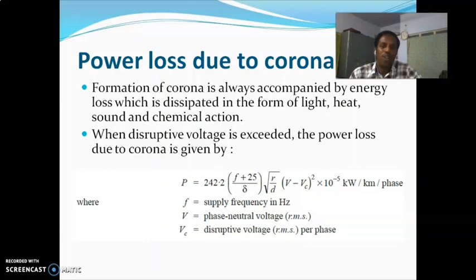So this power loss will be calculated from the given formula. P is equal to 242.2 by delta into (f plus 25) into square root of r by D into (V minus Vc) whole square into 10 power minus 5 kilowatts per kilometer per phase. So f is the supply frequency. Delta, already we know, is the air density factor. V is the actual voltage and Vc is the critical disruptive voltage. From this we can determine the power loss due to the corona.